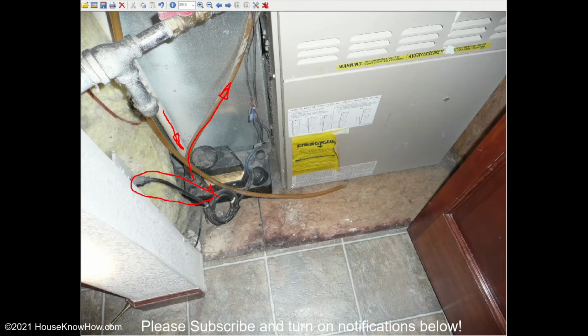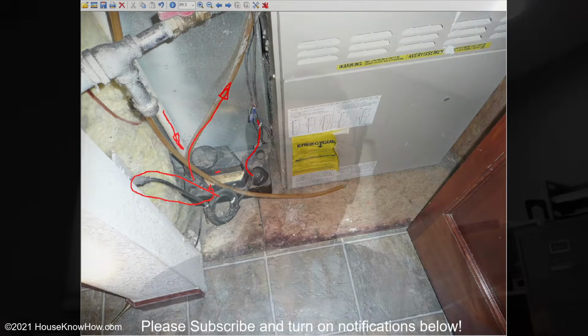There's one more thing that you should do when you install a condensate pump. You should wire the overflow switch into the furnace or air conditioner so that when the pump fails, the furnace or air conditioner won't work. So you know to call for help or to troubleshoot it yourself. And in this picture, these two blue wires are the overflow switch wires.